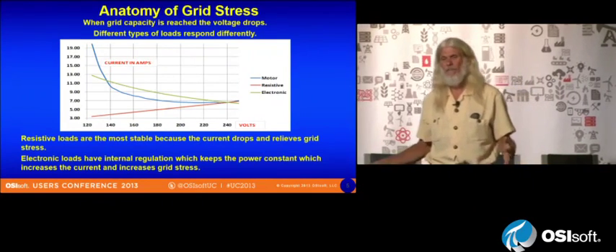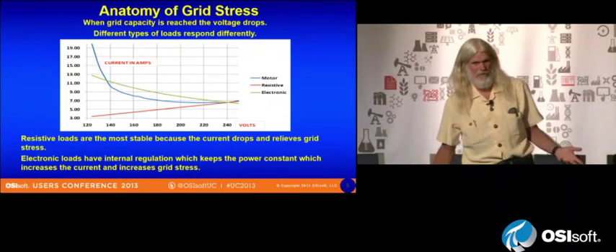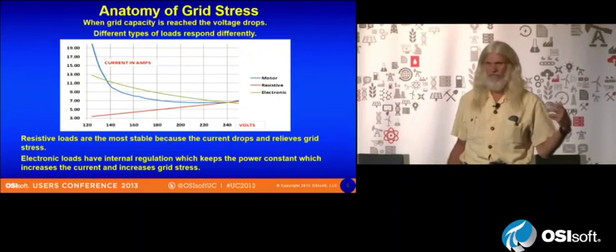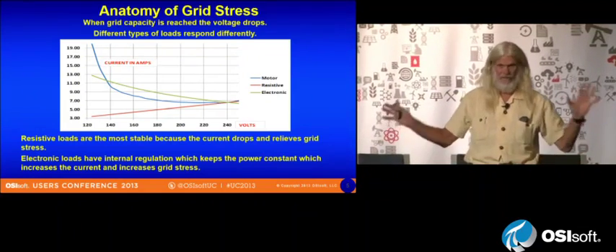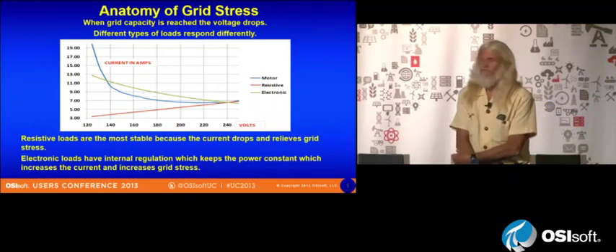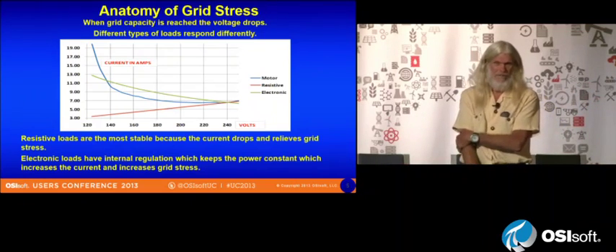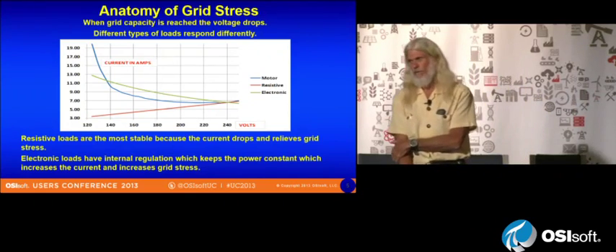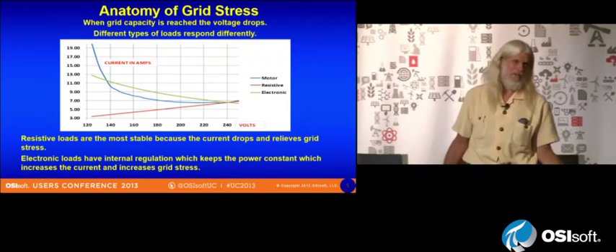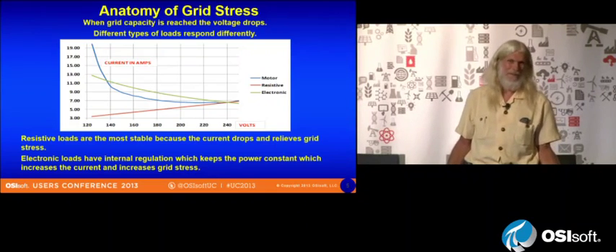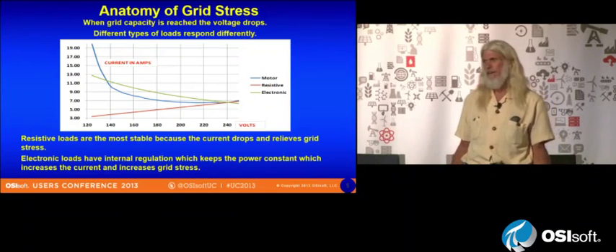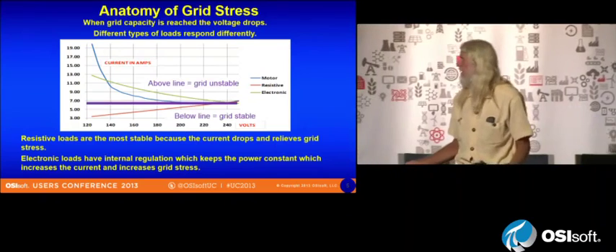But anything with a regulated power supply—compact fluorescent lights, computers, any electronics—means if the voltage dips, the current automatically goes up. What that means is if the voltage is dipping because you've reached capacity, that's going to make it dip even more. In other words, you've created an unstable situation.